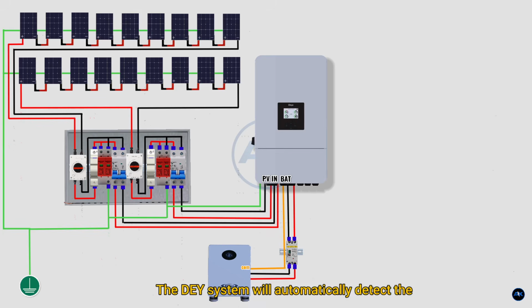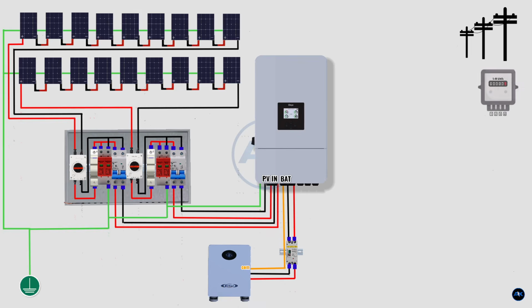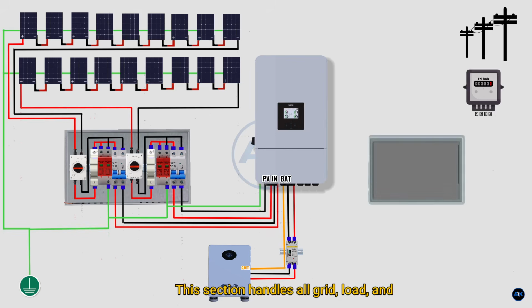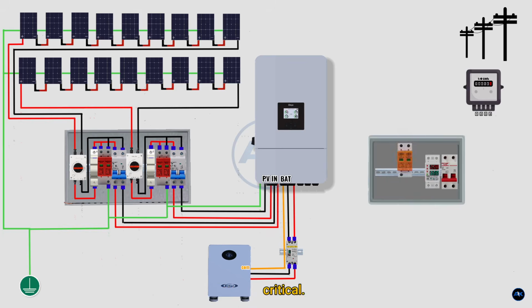The DEYE system will automatically detect the battery's voltage, state of charge, and BMS communication. At this stage, the battery is fully integrated into the DC side of the hybrid energy system. With the battery and solar DC wiring complete, it's time to connect the hybrid inverter to the AC distribution system. This section handles all grid, load, and backup circuits, so accuracy and safety are critical.